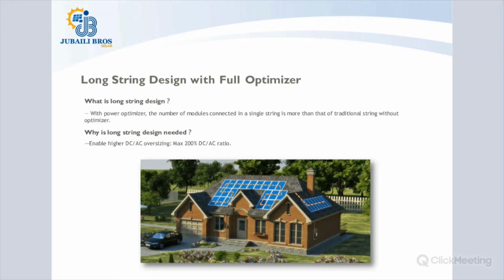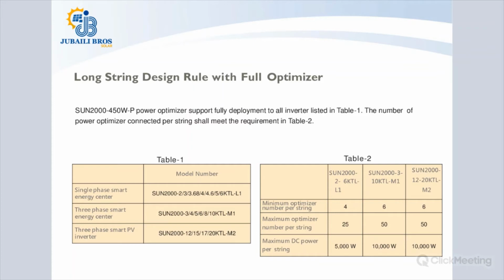In some areas where there is low irradiance around the world, we can go up even up to about 200% DC to AC ratio. And I am particularly talking of areas like Northern Europe, where irradiation is very low. You can go as much as up to 200% of the DC to AC ratio in this region. So let's take a look at what we have here. The long string design rule with the full PV optimizer.